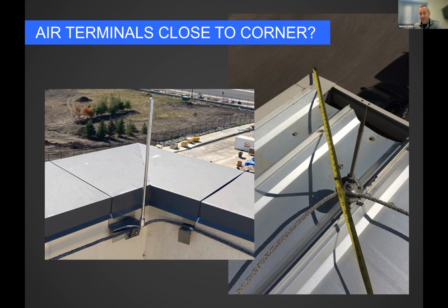On the right is a building I inspected years ago, where someone who wasn't a lightning protection professional installed the system, and it's not 600 millimeters away. It's actually worse, because under the old 1987 code that applied then, you only had to be 500 millimeters from the edge, 4 inches closer. This one's getting on double that.